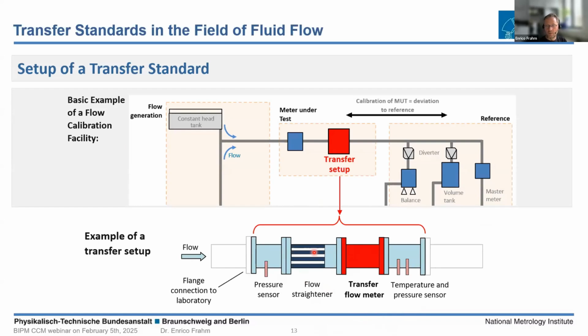And also it is possible to measure special conditions of the calibration, like line pressure at the inflow, line pressure at the outlet, and temperature. So this is a basic drawing of a setup, which we just used in a comparison for large flow.